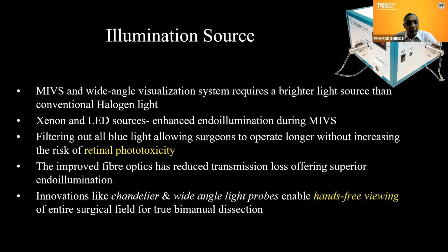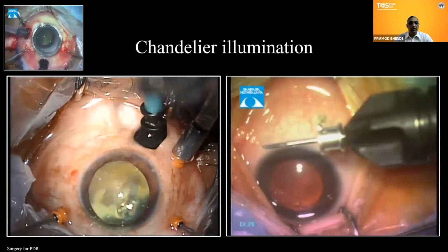So also we have improved fiber optics, which has reduced the transmission losses, offering superior illumination, and the effective illumination you use is much lower now. And we have multiple light probes, like a chandelier, a wide angle light, like a bullet light, which gives hands-free viewing and allows true bimanual surgery. This is just showing one of those cases here.